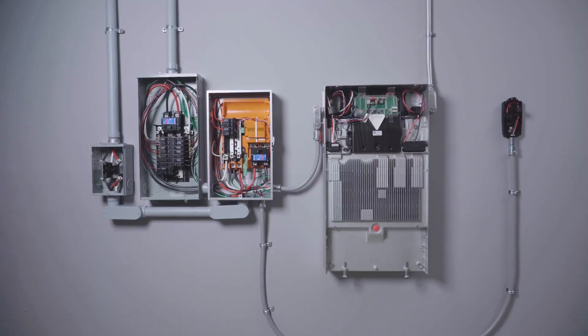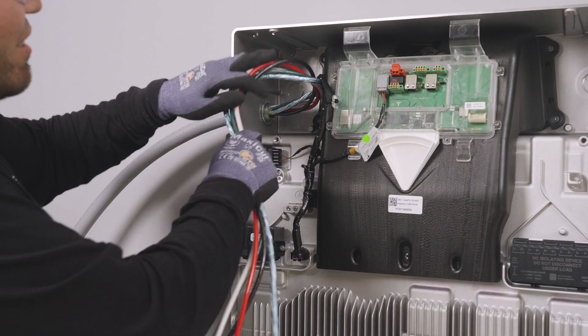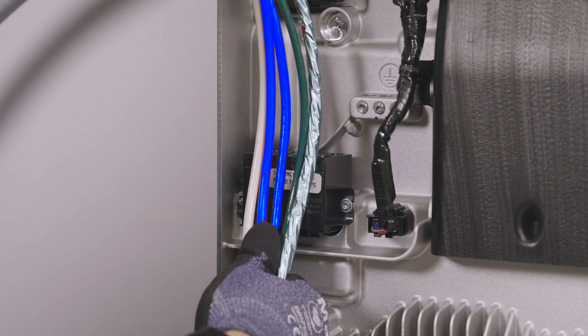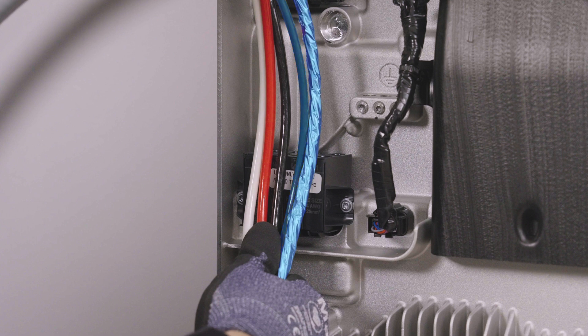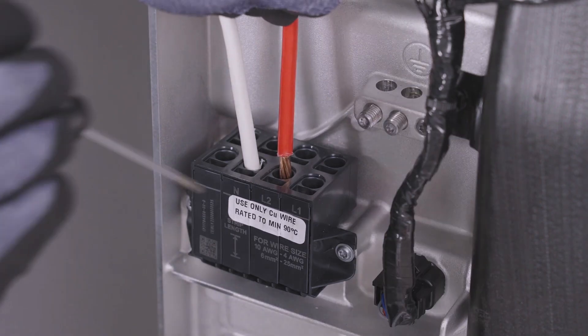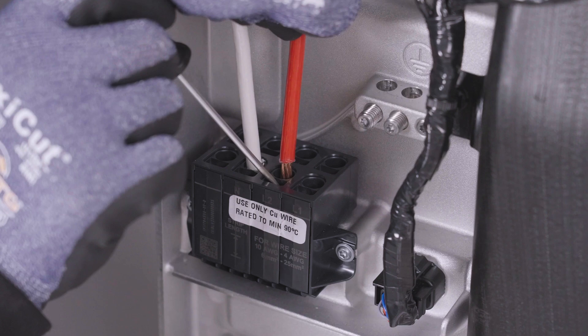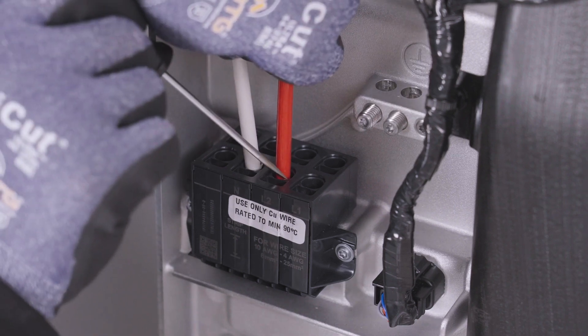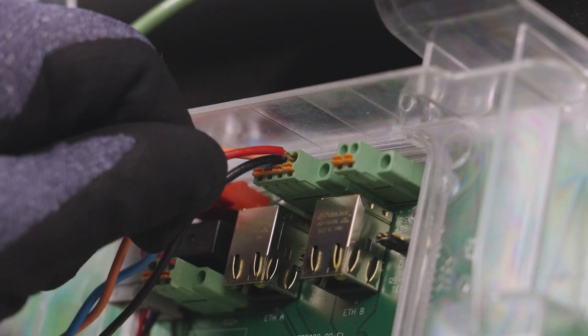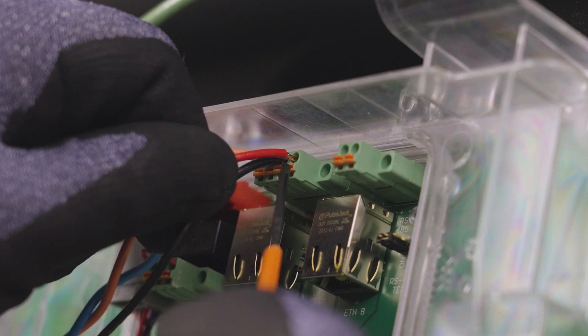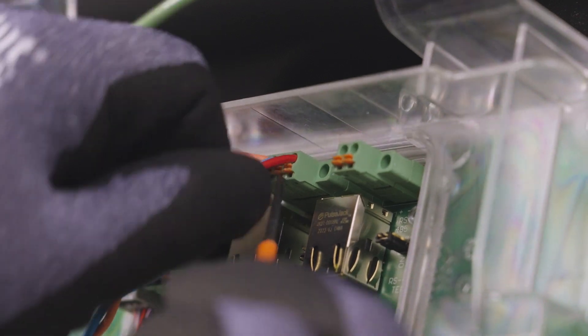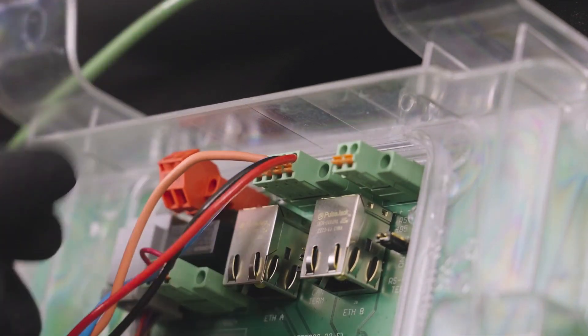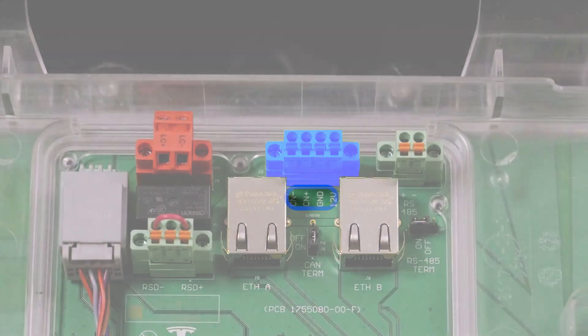Run the branch circuit wiring from Gateway 3 to Powerwall. This will include line 1 and line 2 conductors, a neutral conductor, an equipment grounding conductor, and a 4 wire communication cable. Terminate the branch circuit wiring on the labeled terminals in Powerwall. Communication wiring is landed on these 4 terminals located on the TACO. Terminate each of the 4 conductors on the respective ports as labeled here.